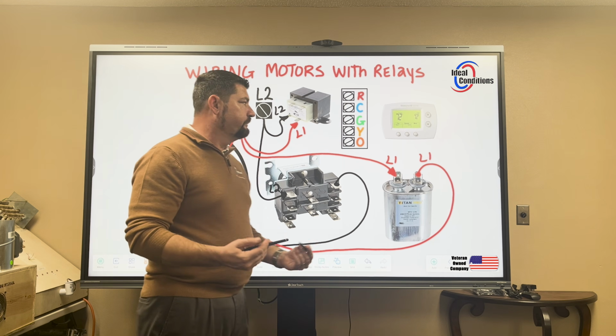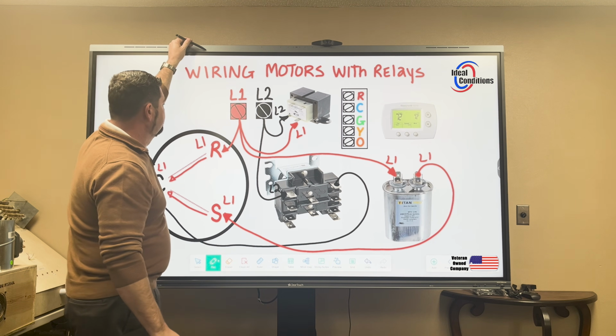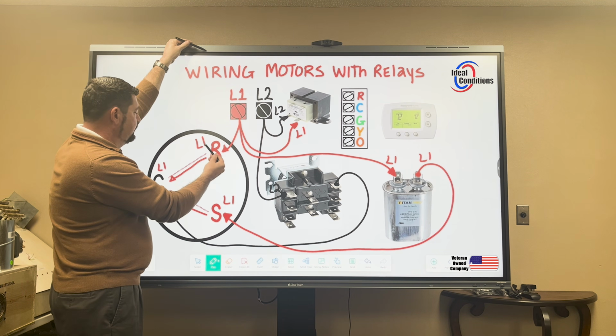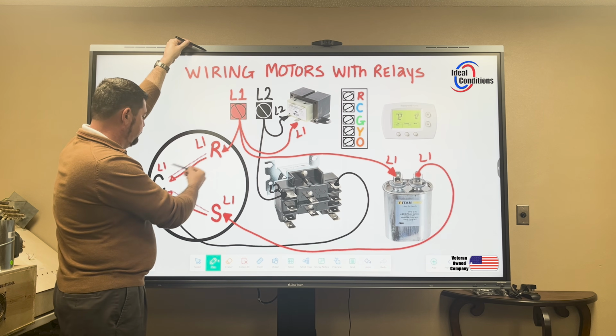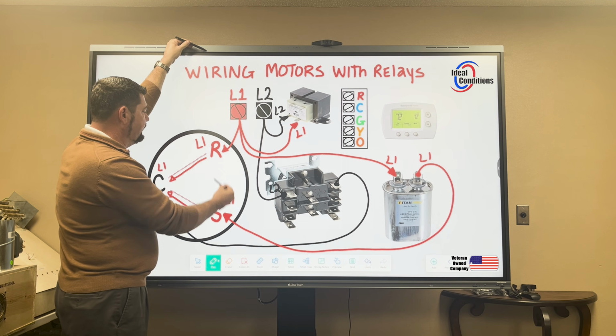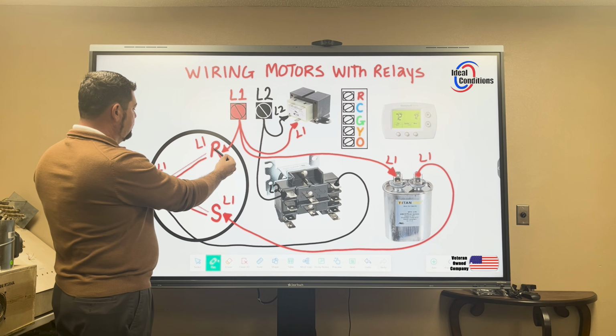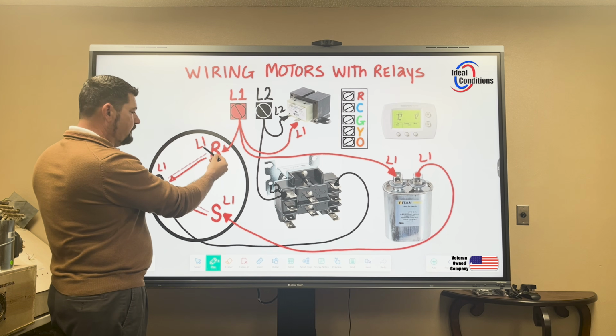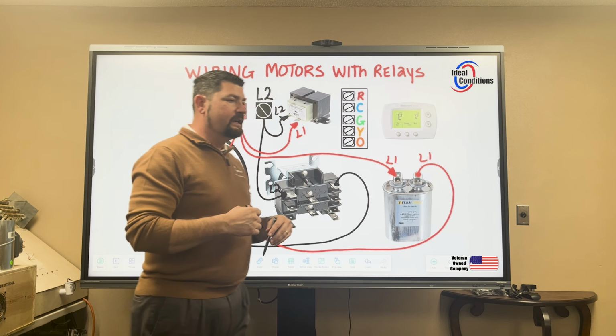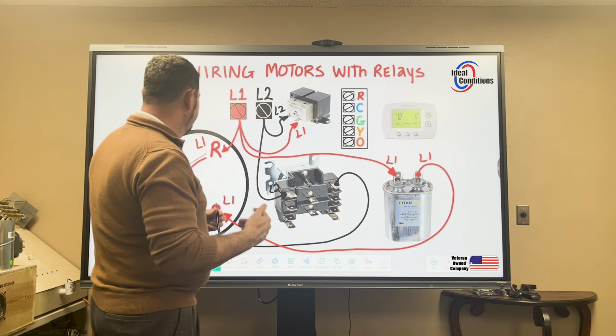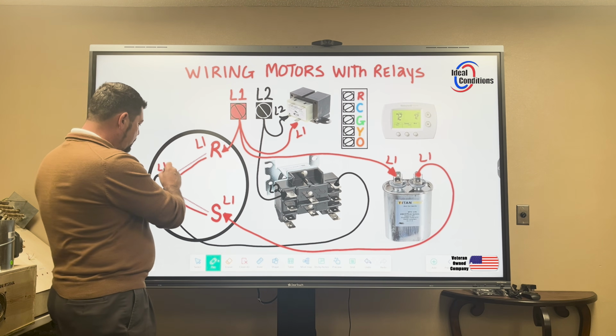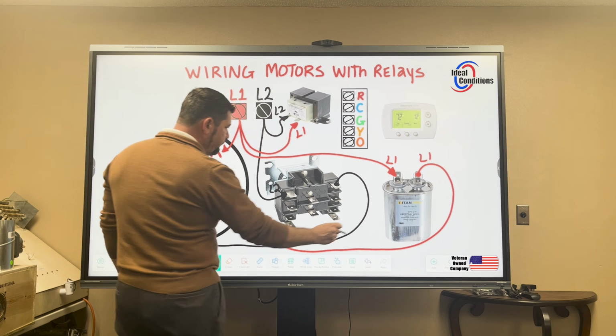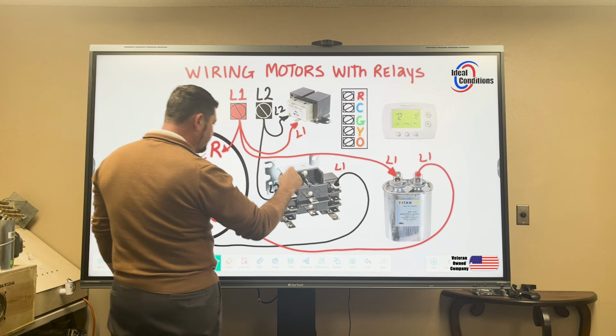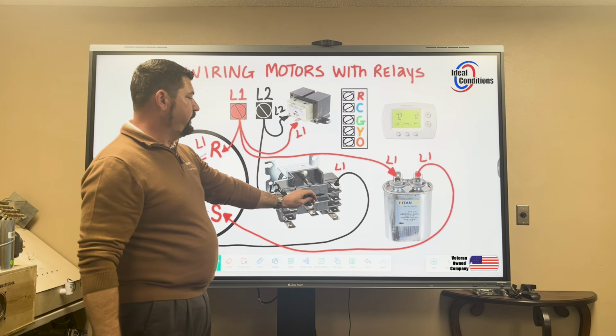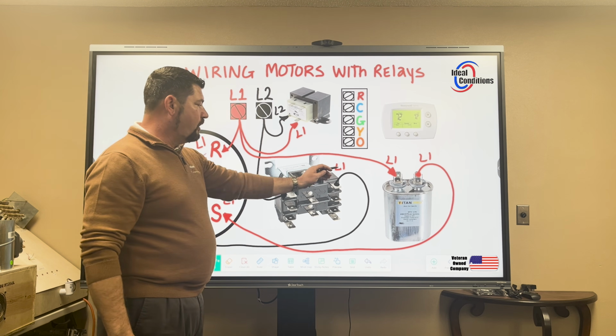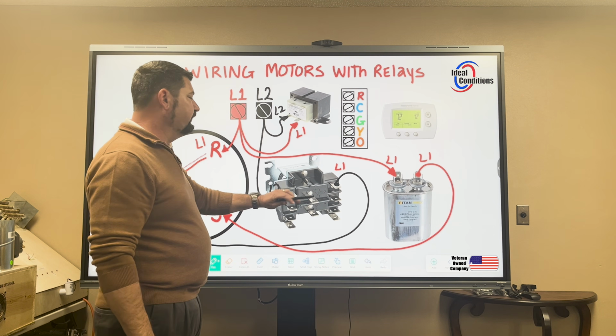It's the same leg. And if I went to ground on one lead and started to touch my other lead to any one of these other respective terminals, I'm going to read one leg of power. But if I come here, at this present time, I'm going to read 0. Not because there's near 0 volts. It's because it's the same leg. So if I'm L1 here, then if you trace it back, that means at this present time, on terminal 3 of the 9340 relay, I'm also L1 there.